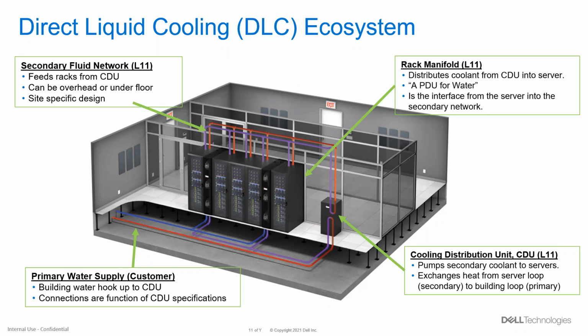What that represents is the coolant that will go at very low pressure, between 0.5 and 1 liter per minute, to the IT through the cold plate loops, capture the heat off of the CPUs, and then take it back to the heat exchanger where, as you can see, the two loops are both in proximity in that central cooling distribution unit. What is happening there is heat is being exchanged to that lower loop. And what that lower loop represents is the customer's facility water loop.